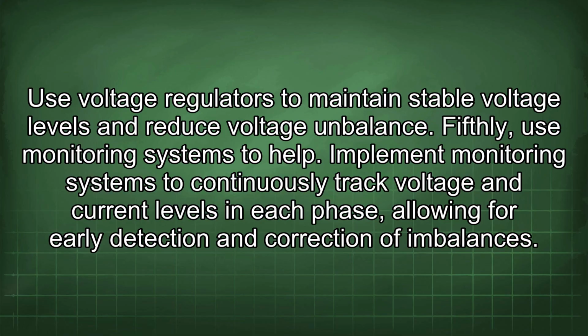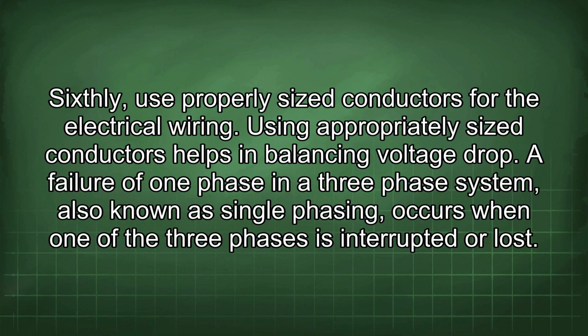Fifthly, use monitoring systems to help. Implement monitoring systems to continuously track voltage and current levels in each phase, allowing for early detection and correction of imbalances. Sixthly, use properly sized conductors for the electrical wiring. Using appropriately sized conductors helps in balancing voltage drop. A failure of one phase in a three-phase system, also known as single phasing, occurs when one of the three phases is interrupted or lost.